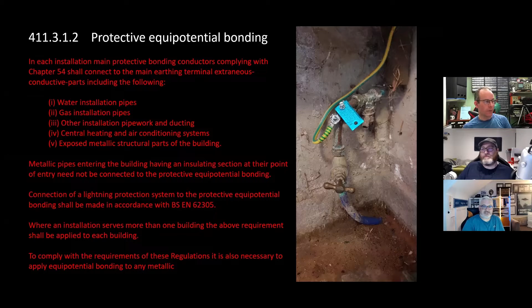So it's none of this - this is the existing reg. This is the new regulation, folks. It now states: in each building, incoming and outgoing metallic parts which are liable to introduce a dangerous potential difference, and do not form part of the electrical installation, shall be connected to the main earthing terminal by protective bonding conductors. Examples of such are metallic water, metallic gas, other ducts. So that list stays the same.